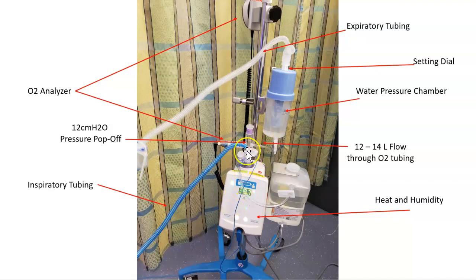Right here is the T-piece that allows for flow. So we have our T-piece here. We have our oxygen tubing right here, providing 12 to 14 liters of oxygen that is titrated based off the wall blender. This is a pop-off that is set at 12 centimeters of water pressure. So if our pressure is climbing for whatever reason, it will hiss, and then it will alert you that you're getting up to 12 centimeters of water pressure. The other is the oxygen analyzer that goes in on the other side to help close off this system and allow us to read what we are actually delivering to our patient.